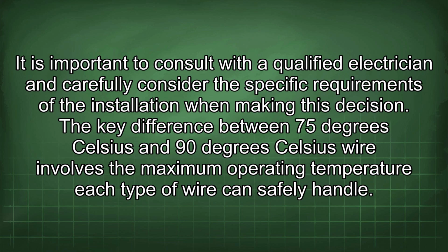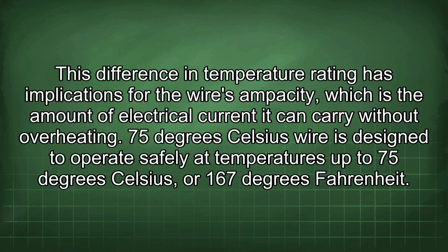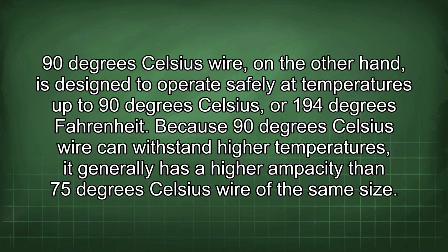The key difference between 75 degrees Celsius and 90 degrees Celsius wire involves the maximum operating temperature each type of wire can safely handle. This difference in temperature rating has implications for the wire's ampacity, which is the amount of electrical current it can carry without overheating. 75 degrees Celsius wire is designed to operate safely at temperatures up to 75 degrees Celsius or 167 degrees Fahrenheit. 90 degrees Celsius wire, on the other hand, is designed to operate safely at temperatures up to 90 degrees Celsius or 194 degrees Fahrenheit.